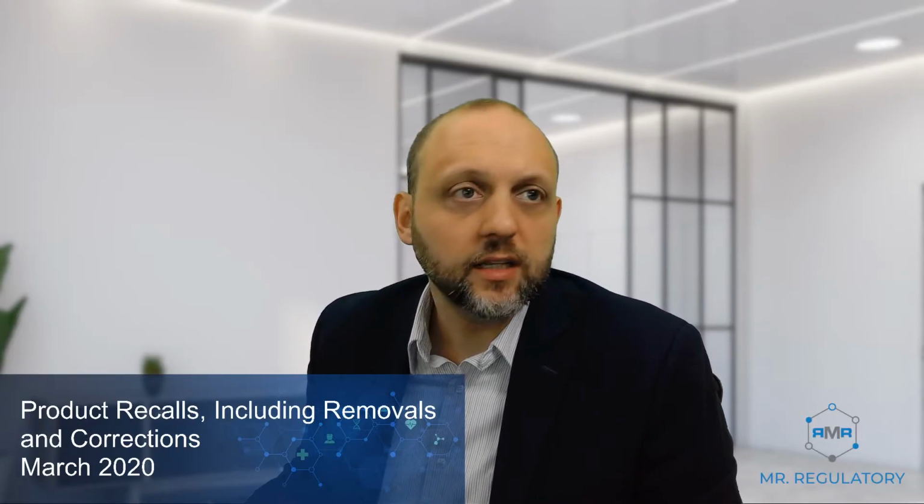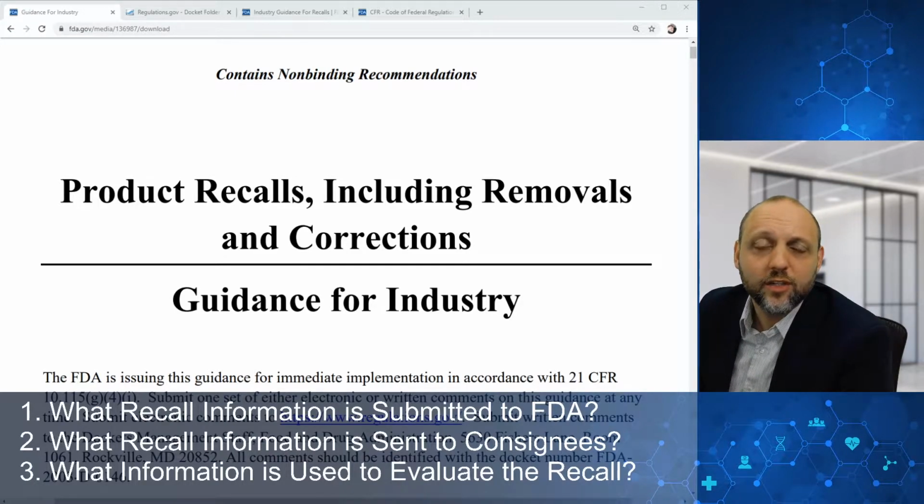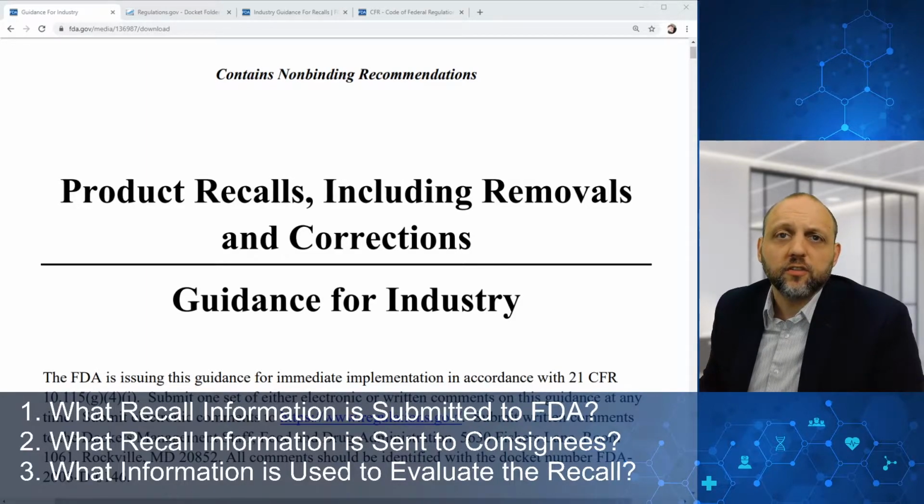There are just a couple things that I'd like you to take away from today's video, and those things are, one, what recall information is submitted to FDA, so what is required in that document package that you're going to have to submit to FDA. Number two, what recall information is sent to your consignees, that would be your end users or your customers, and also what information is used to evaluate the recall, the effectiveness, and also to close out the recall with FDA. So without much further ado, let's go ahead and get into it.